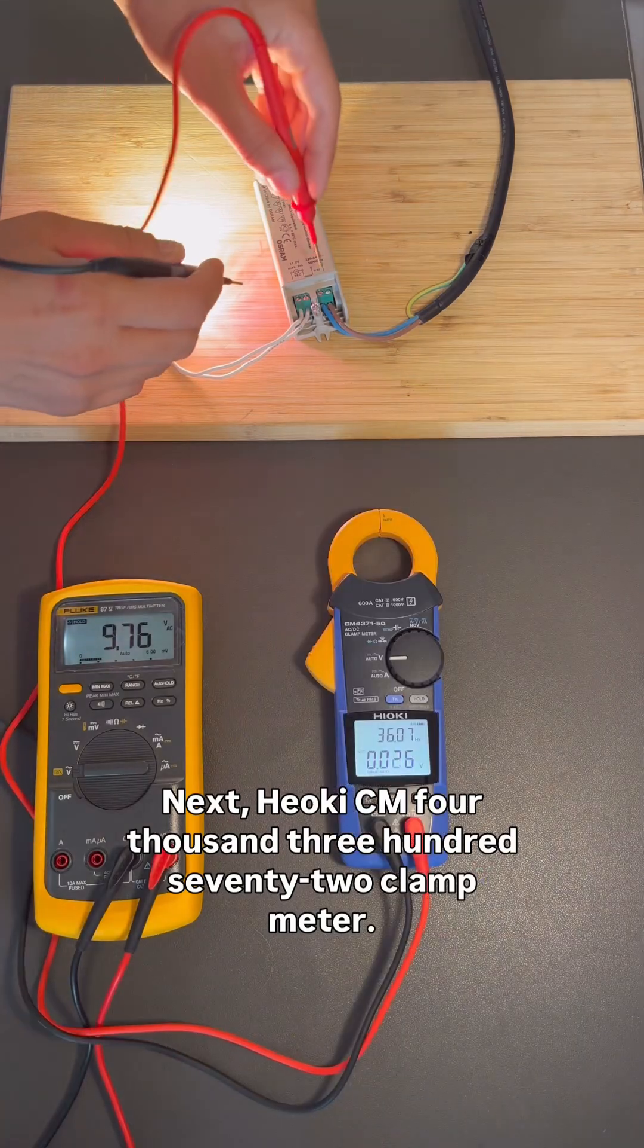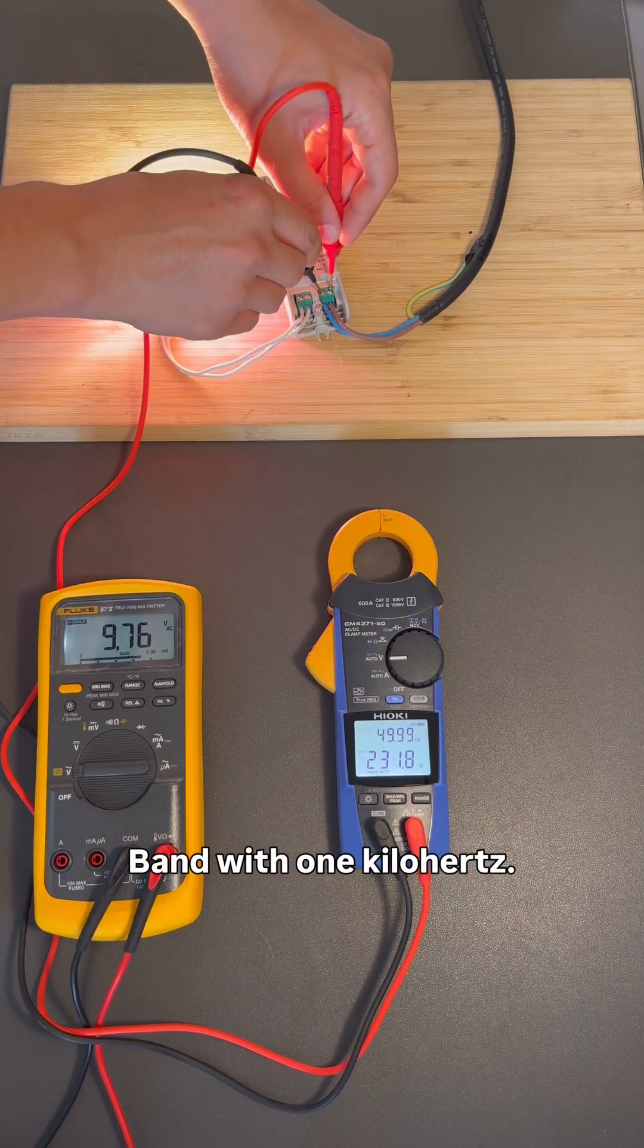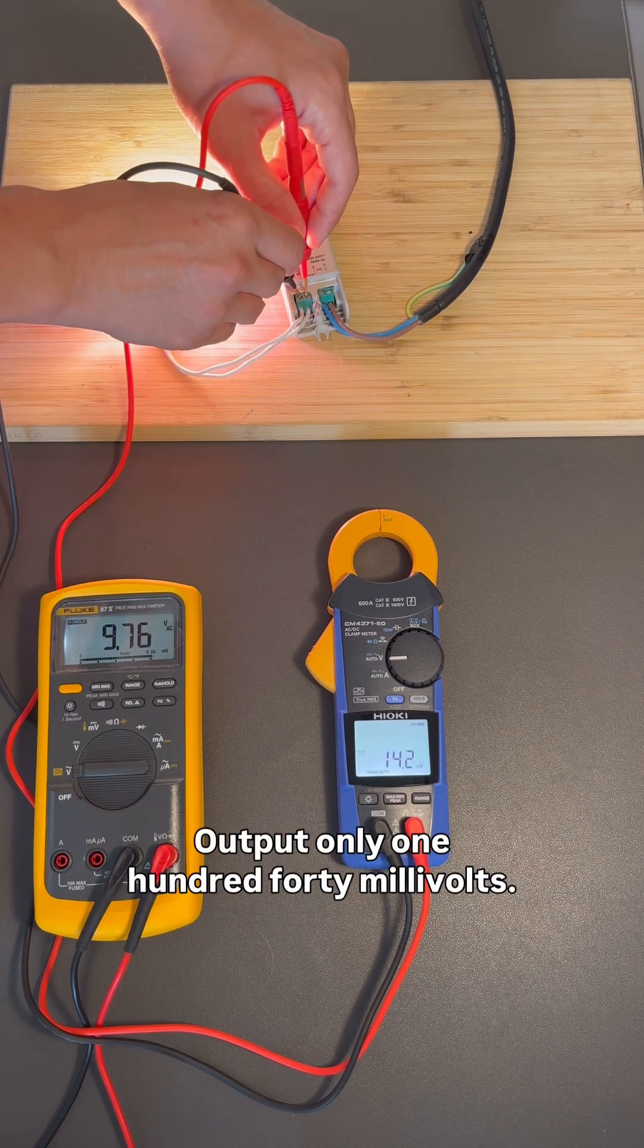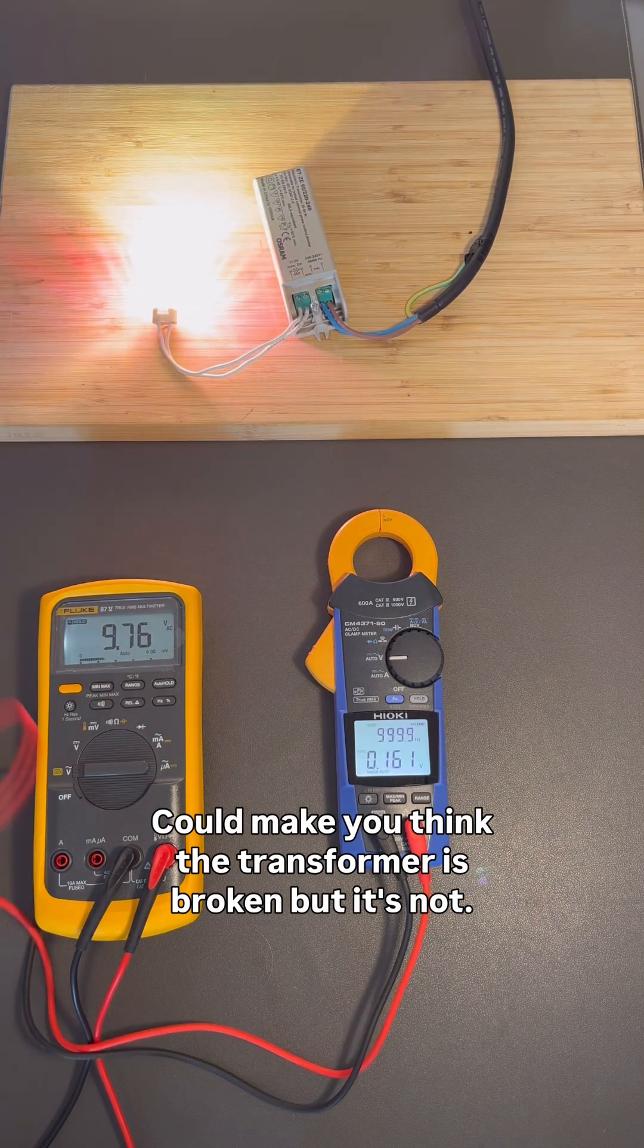Next, Hioki CM4372 clamp meter. Bandwidth, 1kHz. Input, 50Hz. Fine. Output, only 140mV. Could make you think the transformer is broken. But it's not.